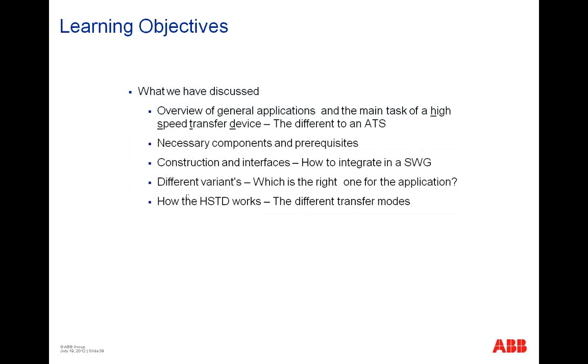So, we are nearly at the end. What we have discussed, yes, we have discussed the general applications for the HSTD, and the main task. Yes, the main task is to keep everything alive. The difference to an ATS, I would say now, a stupid device, opens only the main feeder, waits a certain time, then closes the standby feeder. That's very easy, but you have really no benefit.